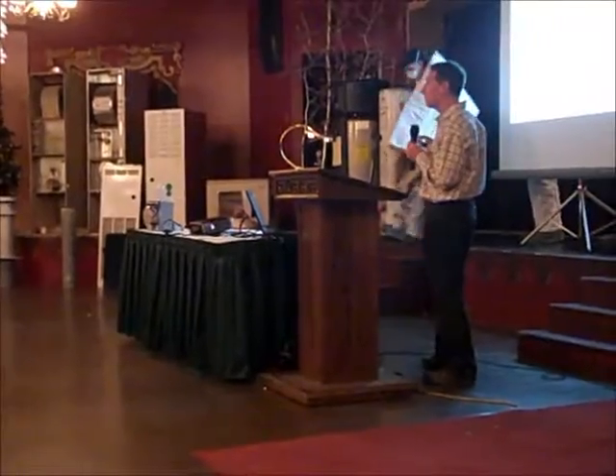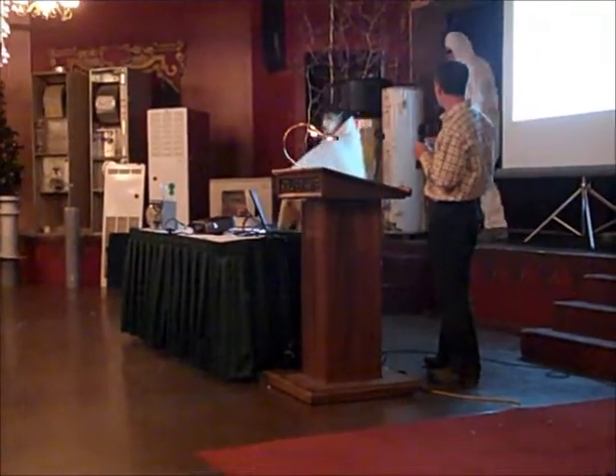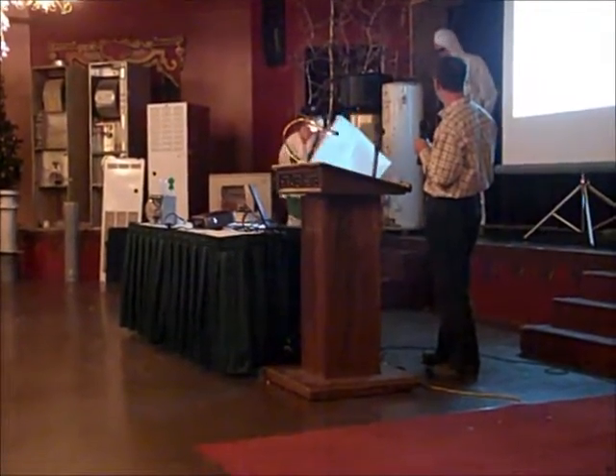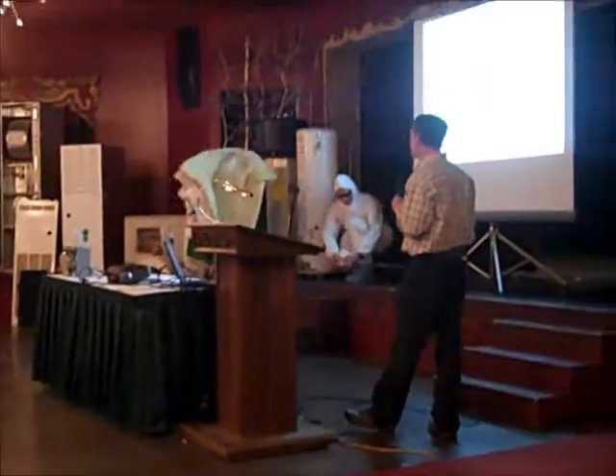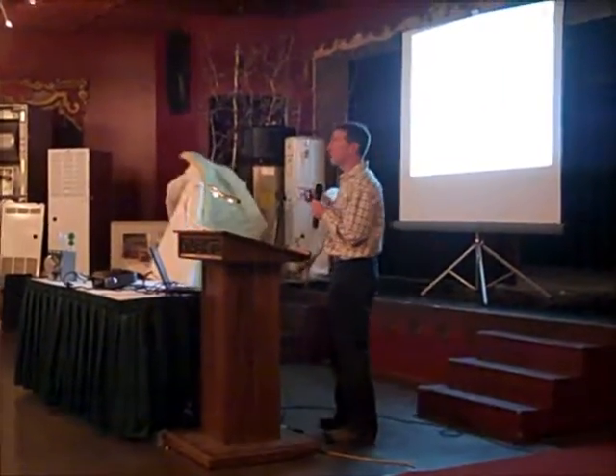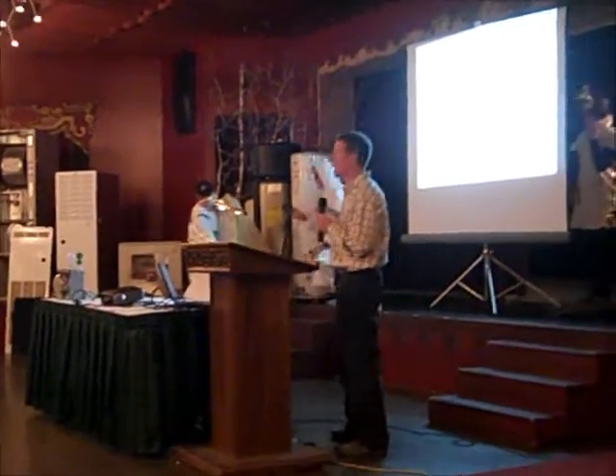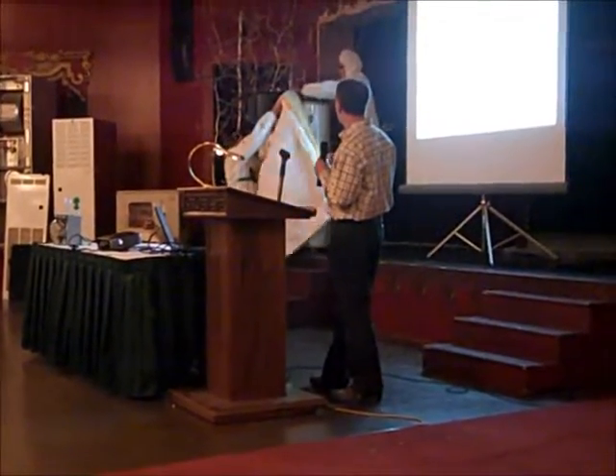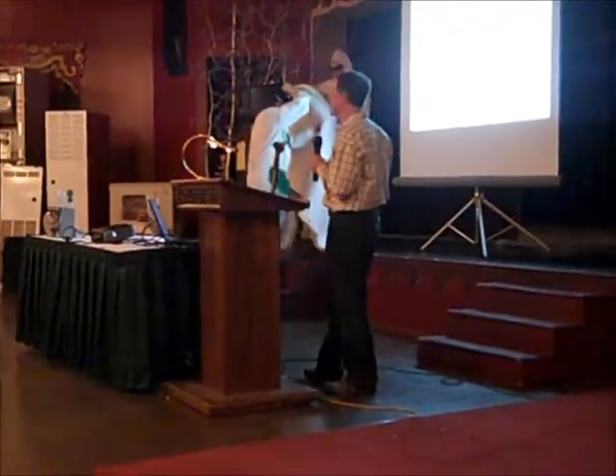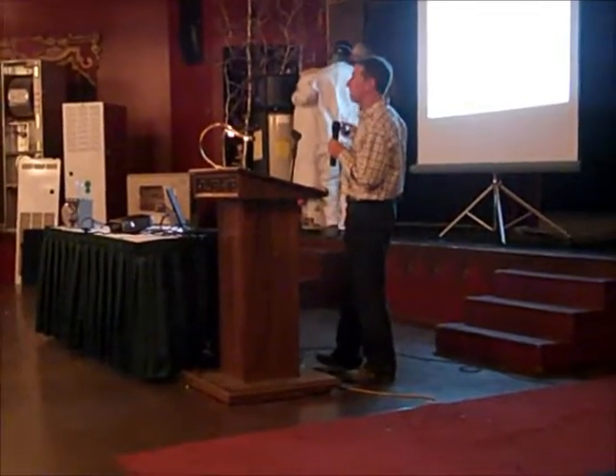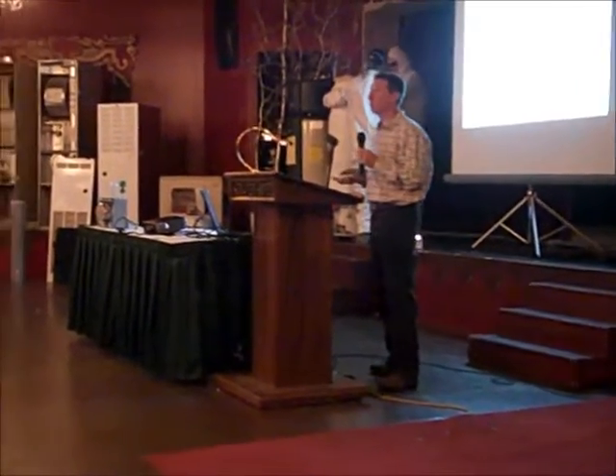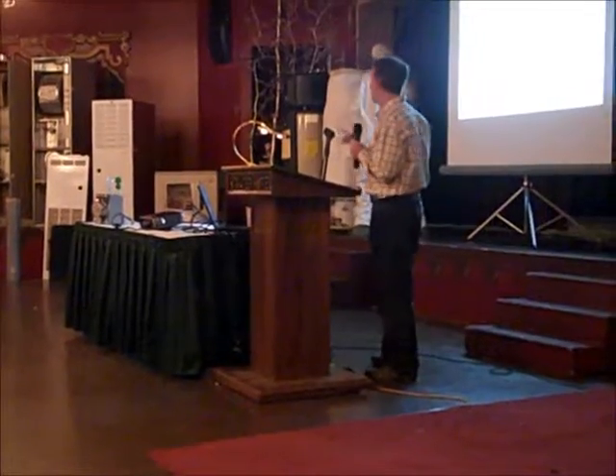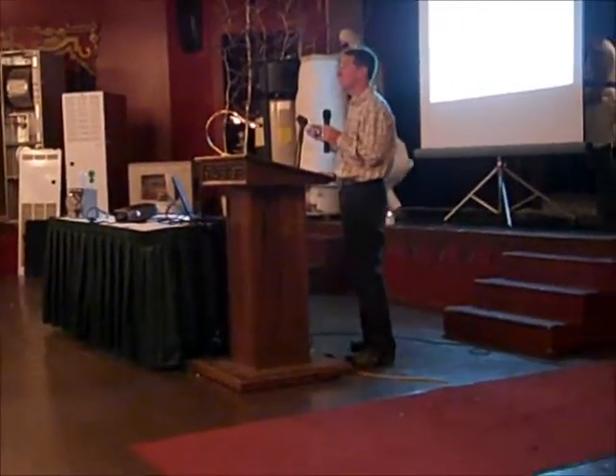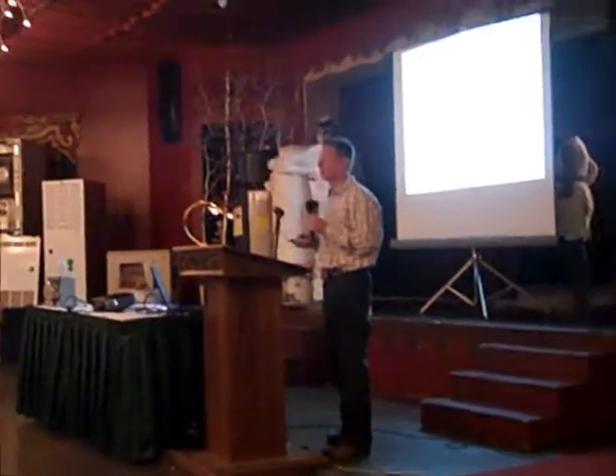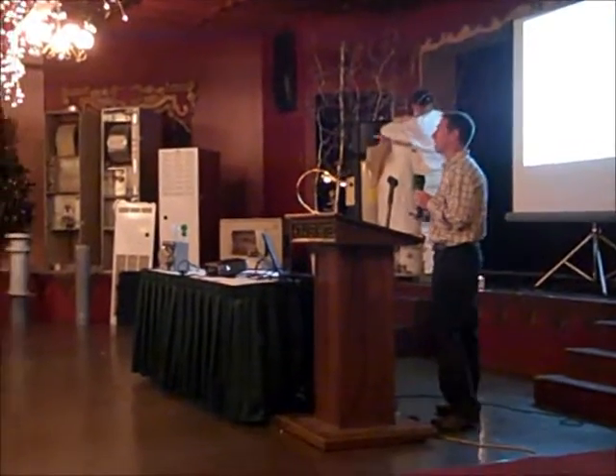But does your water heater have a blanket? So we have the water heater blanket. We might need to move the pilot light before we wrap that. But we'll leave that candle burning. Now when we say atmospheric, you do want to be careful if you're wrapping an atmospheric water heater with a blanket. You need to get combustion air to it. This would have a vent stack that would hopefully go through your roof and vent to the outside. Although as many of our auditors will attest, some people just vent theirs right into their room. And when we get there, they're like, I don't know why I have a headache.